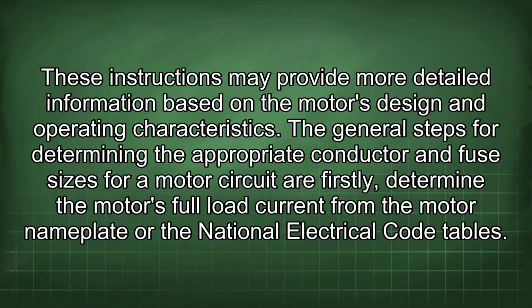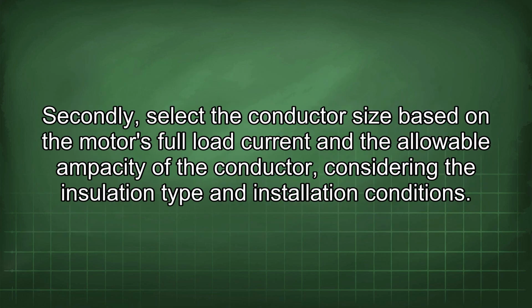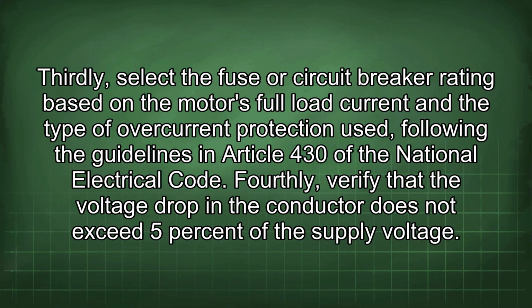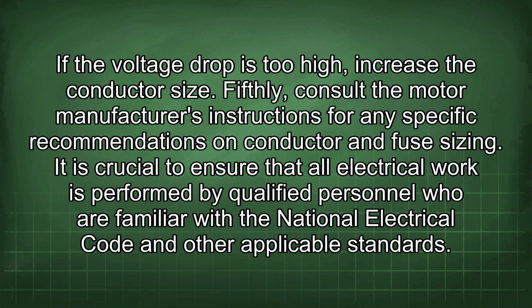The general steps for determining the appropriate conductor and fuse sizes for a motor circuit are: firstly, determine the motor's full load current from the motor nameplate or the National Electrical Code tables. Secondly, select the conductor size based on the motor's full load current and the allowable ampacity of the conductor, considering the insulation type and installation conditions. Thirdly, select the fuse or circuit breaker rating based on the motor's full load current and the type of overcurrent protection used, following the guidelines in Article 430 of the National Electrical Code. Fourthly, verify that the voltage drop in the conductor does not exceed 5% of the supply voltage. If the voltage drop is too high, increase the conductor size. Fifthly, consult the motor manufacturer's instructions for any specific recommendations on conductor and fuse sizing.